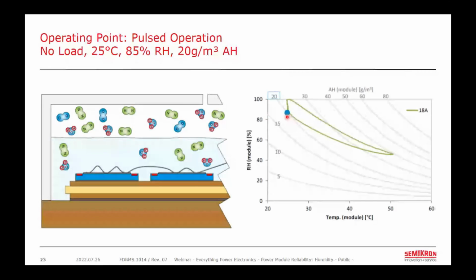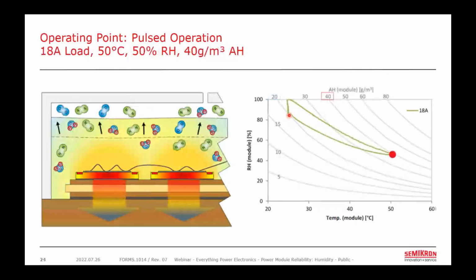And by looking at the climatogram here, we can see that the absolute humidity line that we happen to be on is 20 grams per cubic meter. Now we're going to apply an 18 amp pulse of current to this module for some minutes. So the chips begin to heat up because of the conduction losses in the chip. And this heat raises the temperature of the module from 25 degrees C up to 50 degrees C, as shown by this red dot in the diagram where we are now. We can see that the relative humidity drops from 85% down to 50%, as we expected from earlier discussion.